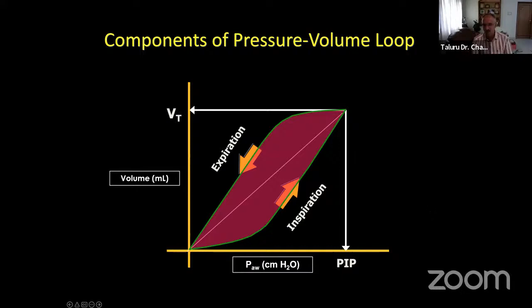See, if you are talking of a volume mode or a volume limited mode, that means this line is fixed. This line is fixed. So whenever the compliance changes, tidal volume will be generated 400 ml, but the pressure will keep on moving in this direction. In a pressure mode, this will be set. The volume line will be moving down. So you can understand modes also by looking at this. I have not put those slides because of want of time. In the slides that I'm going to send, I put that also. You can go through that.